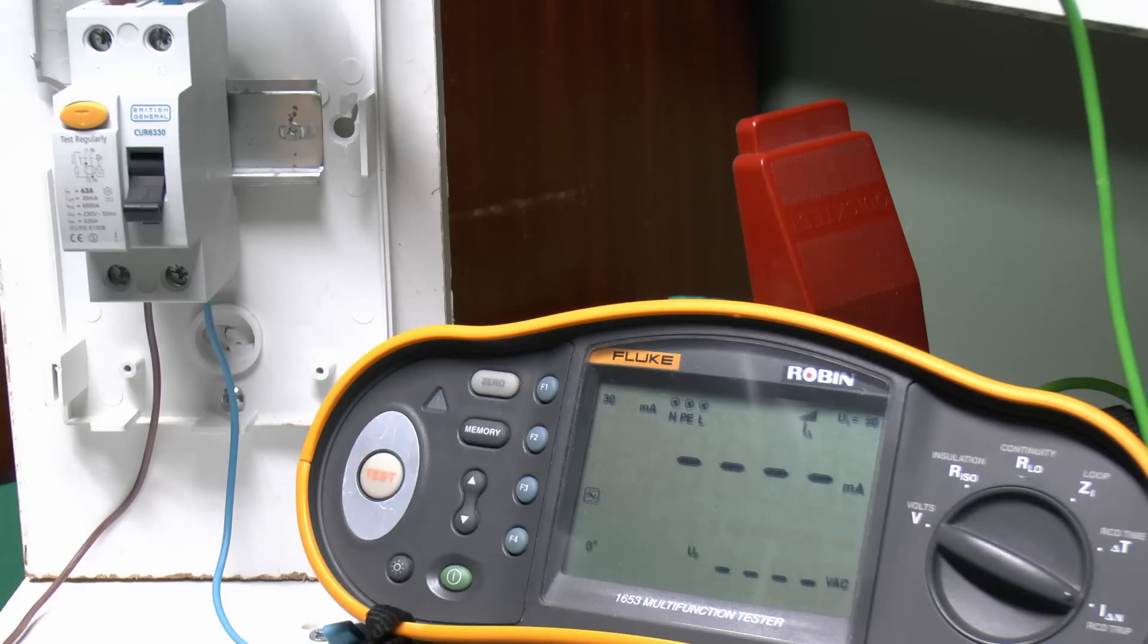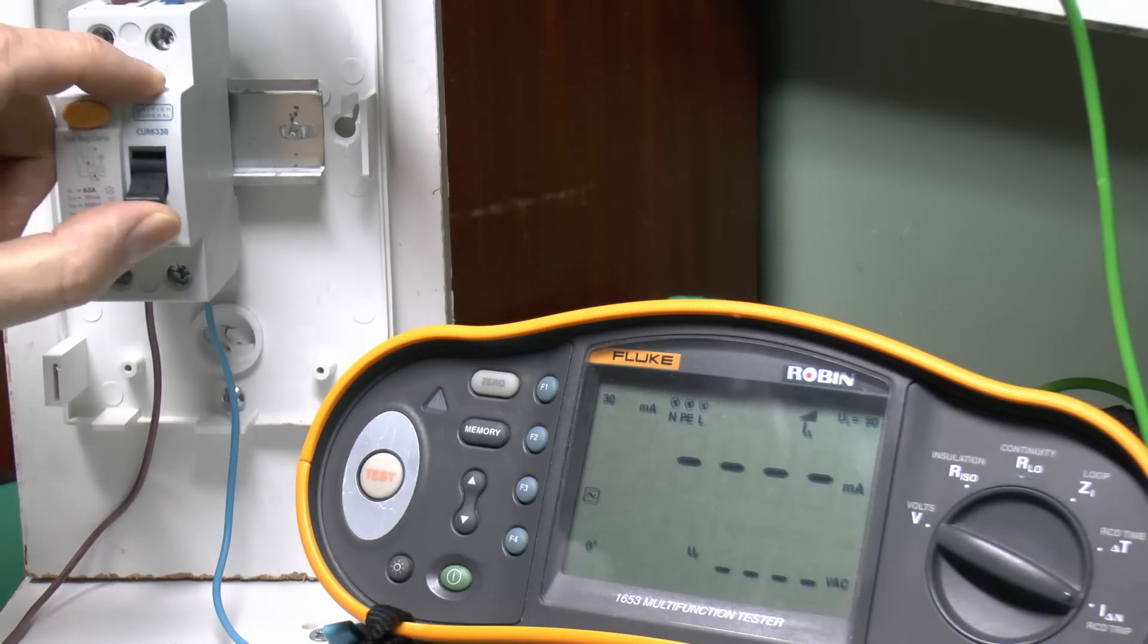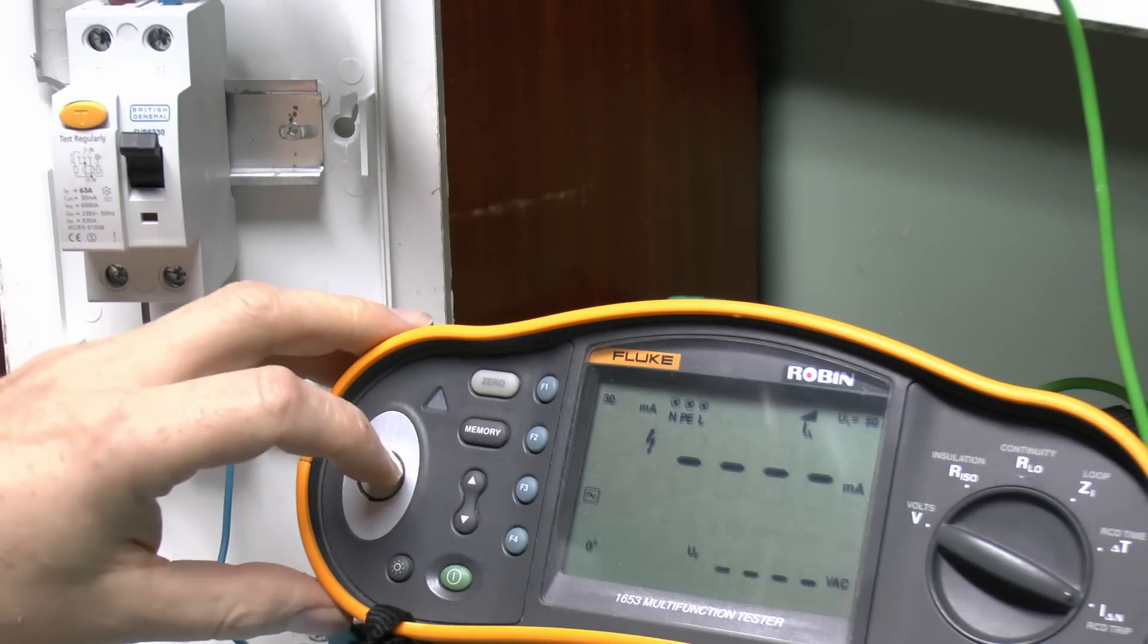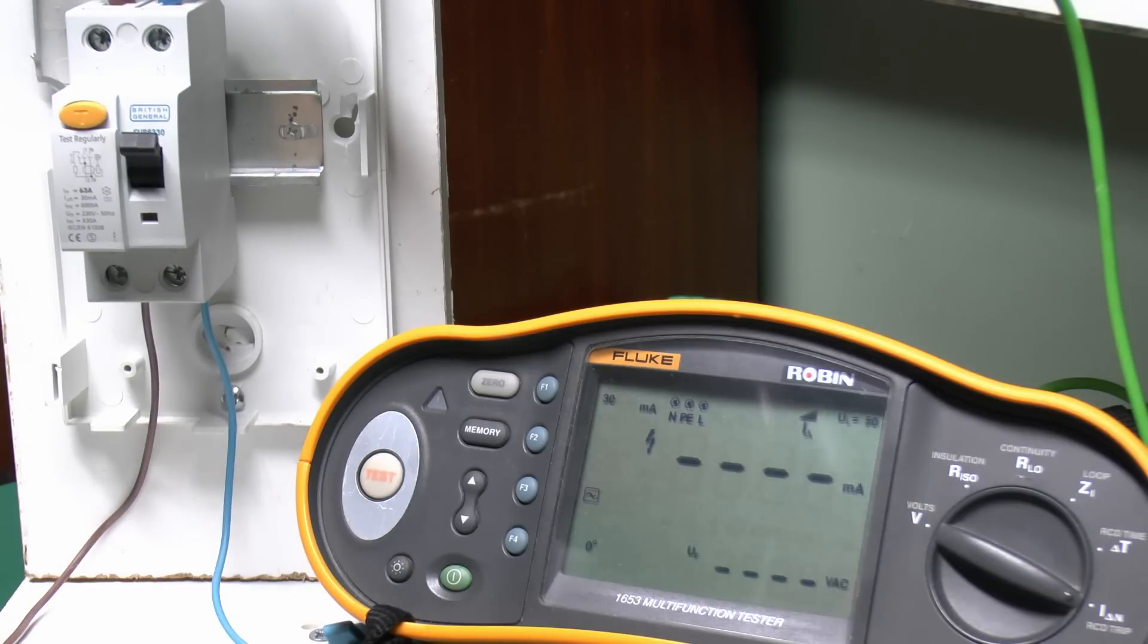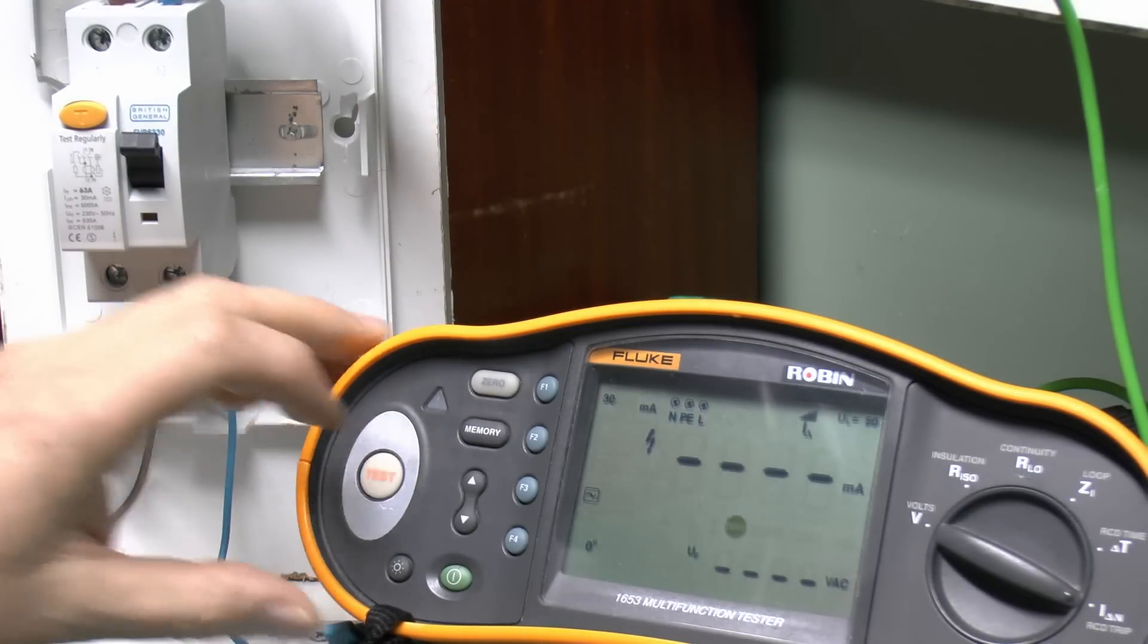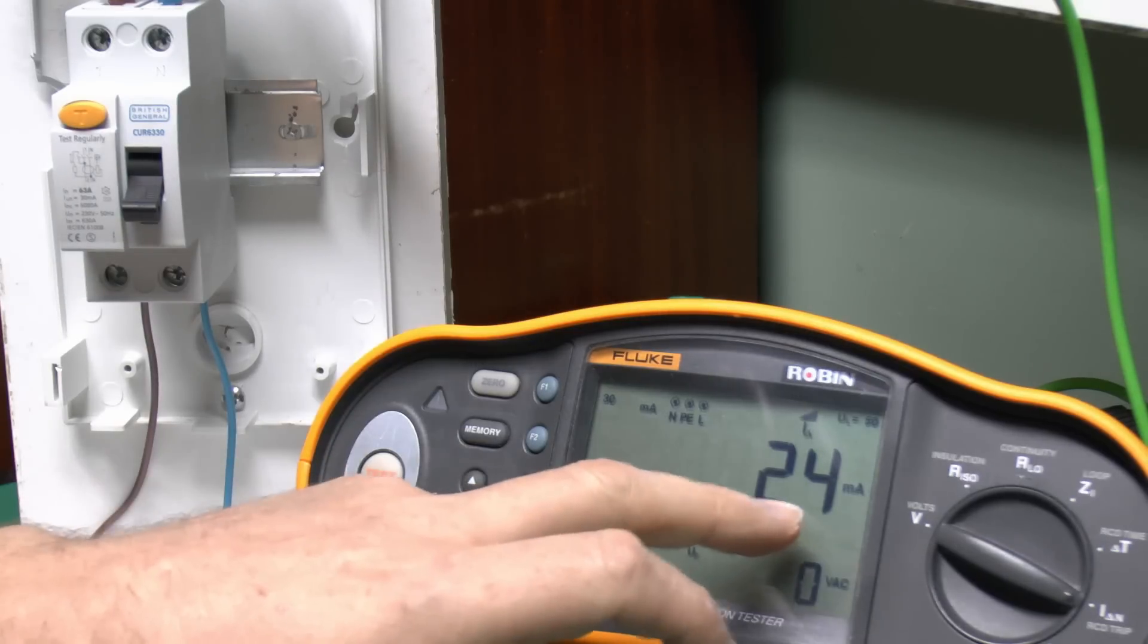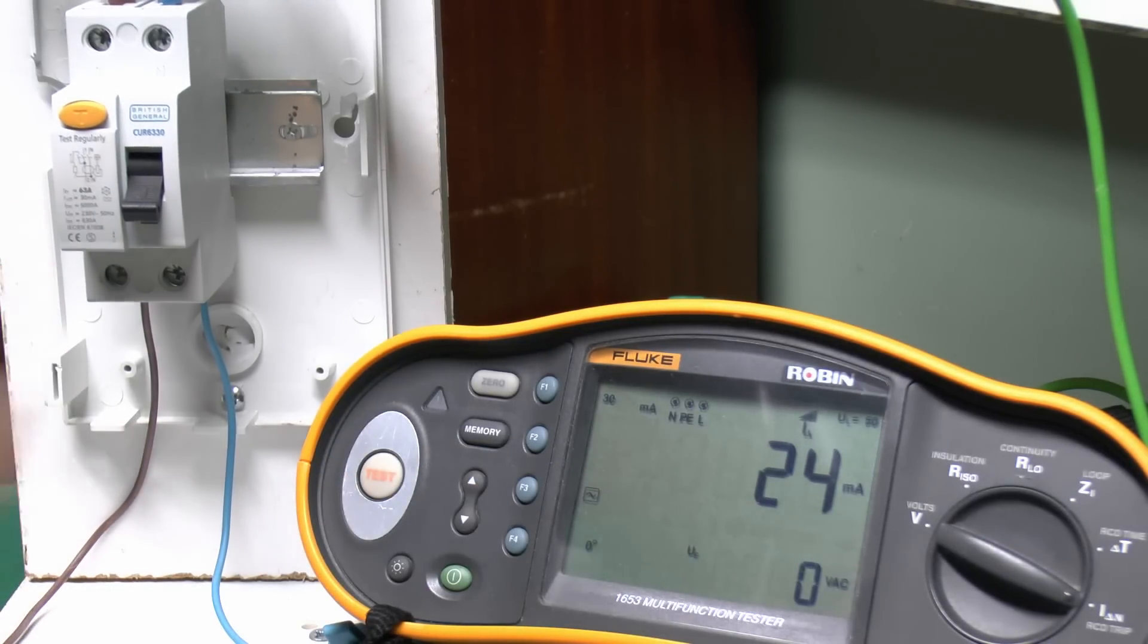So once we've done those, we can switch on the power here, and just switch on the actual device, and then a simple question of pressing the test button. What will happen is it will gradually increase the current between here and here until the device trips, and then it will just display the actual current that the device tripped at on the front there. So in that case, we've got a current there of 24 milliamps, which is perfectly acceptable. So this is a 30 milliamp device, but 24 is perfectly fine.